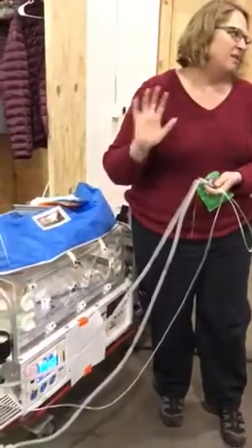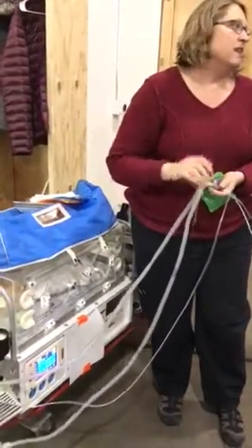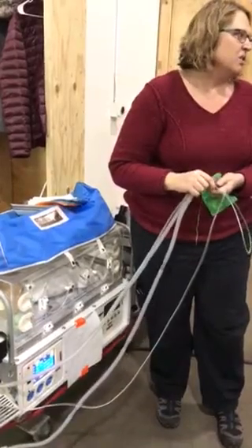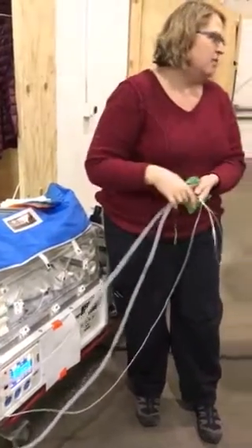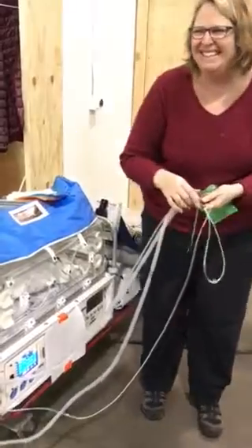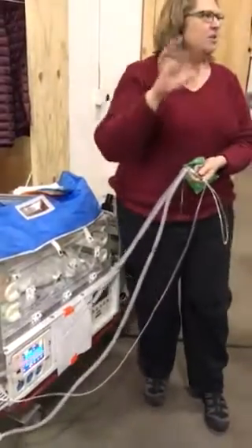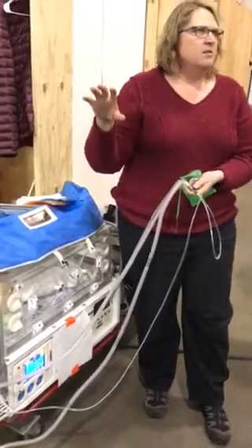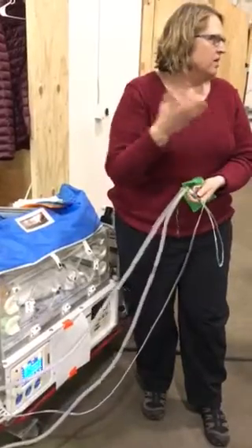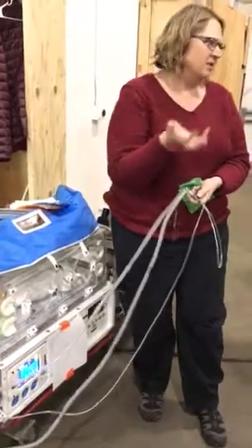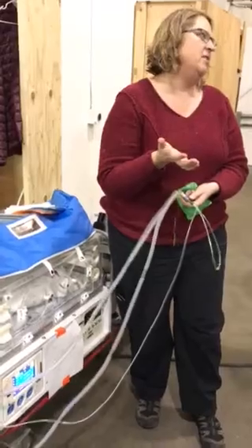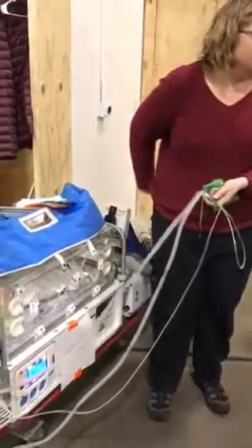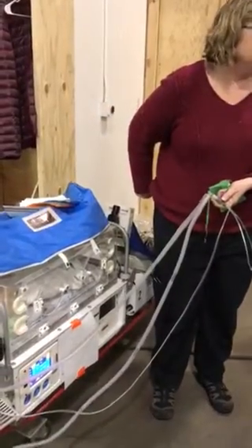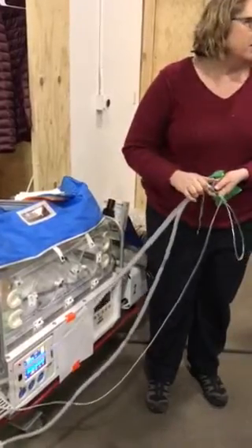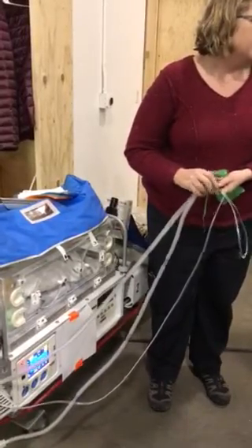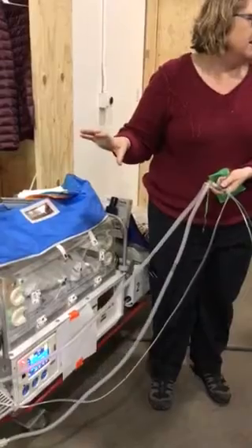So this is just running the ventilator, is all it's doing. Okay. That's a good question. I usually set it on 8. Yeah, I don't know why. I like that number. It doesn't matter. I think it's what you use to hook up your bag and mask from a wall, like 8 usually is where it'll drive your flow enough. If you're running out of air and oxygen and you're like, oh, we're not going to make it, you could go down to 6 even. I've seen some of them.